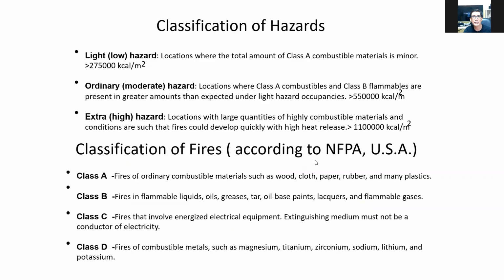No? So another one is the classification of hazards. We have the light hazard, ordinary, or the extra high hazard. The light hazard is where the total amount of Class A combustible materials is minor, or less than 275,000 calorific per square meter. Another one is ordinary or moderate, which is less than 550,000 calorific value. Then if you have a high hazard location with large quantities of highly combustible materials, and conditions such that fire could develop quickly with a high rate of release, that is more than 1.1 million calorific value per square meter. So this classification of hazards, you can base on the calorific value per square meter.